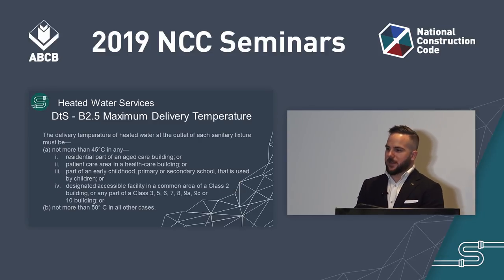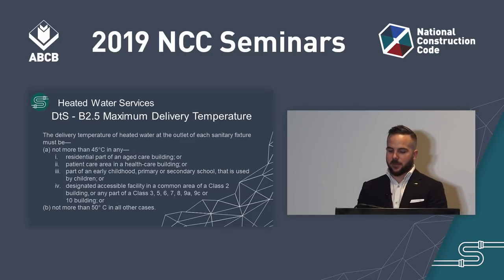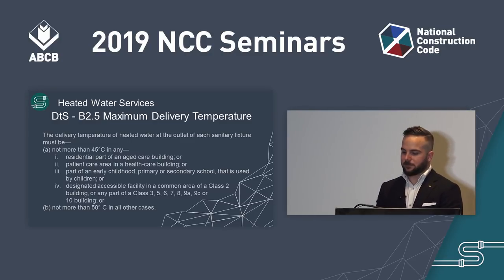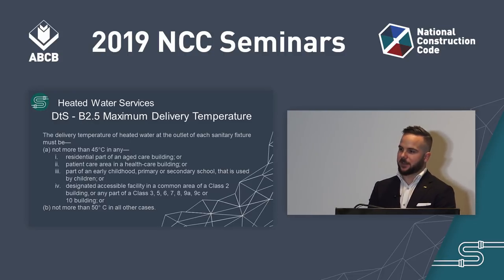There are also new deemed-to-satisfy provisions. B2.5, maximum delivery temperature, applies only to new heated water installations for the purpose of personal hygiene. It states that the delivery temperature of heated water at the outlet of each sanitary fixture must not be more than 45 degrees Celsius in any aged care building, health care building, early childhood centre, primary or secondary school, or a designated accessible facility, and not more than 50 degrees Celsius in any other cases.